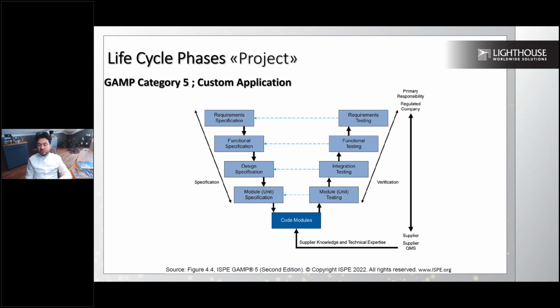Then the code modules are put together, the system is installed, and testing the modules is known as installation qualification. The integration testing also addresses the functional specifications, and the functional testing addresses the requirements from day one, ensuring the system is suitable for its intended use.